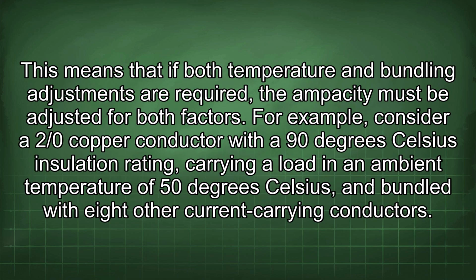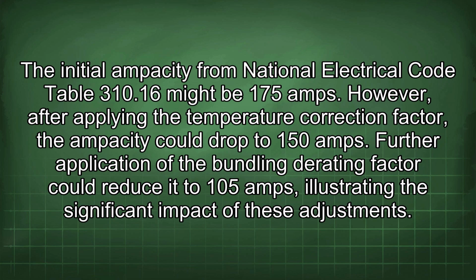These correction and derating factors are multiplicative. This means that if both temperature and bundling adjustments are required, the ampacity must be adjusted for both factors. For example, consider a 2/0 copper conductor with a 90 degrees Celsius insulation rating, carrying a load in an ambient temperature of 50 degrees Celsius, and bundled with 8 other current-carrying conductors. The initial ampacity from National Electrical Code Table 310.16 might be 175 amps. However, after applying the temperature correction factor, the ampacity could drop to 150 amps. Further application of the bundling derating factor could reduce it to 105 amps, illustrating the significant impact of these adjustments.